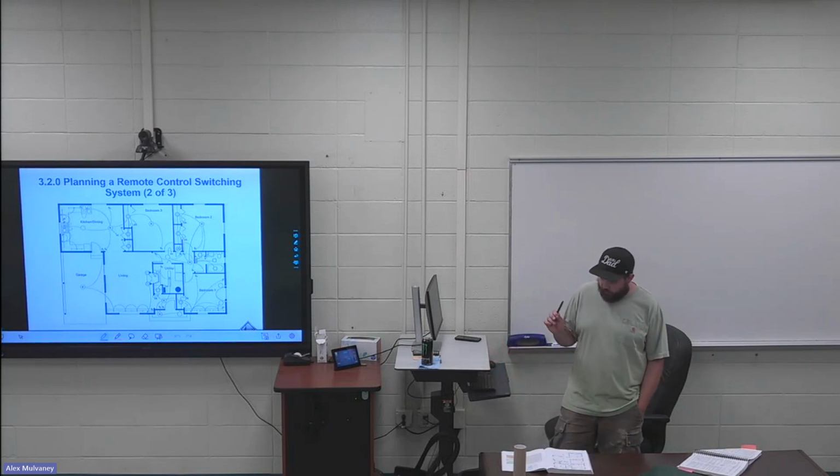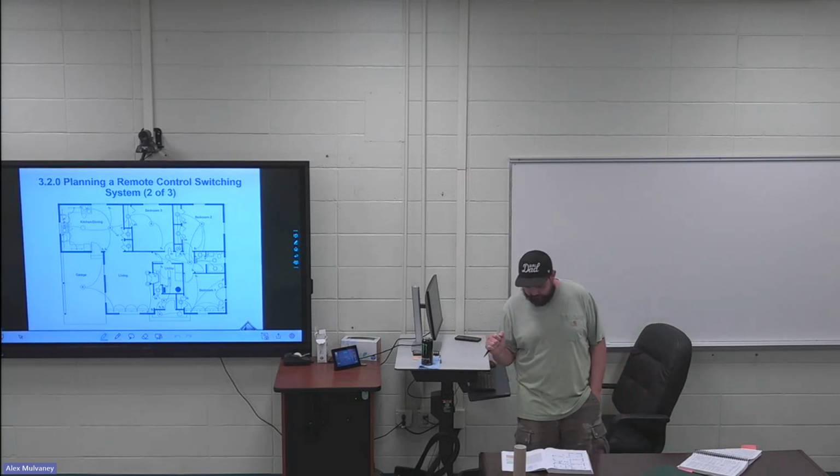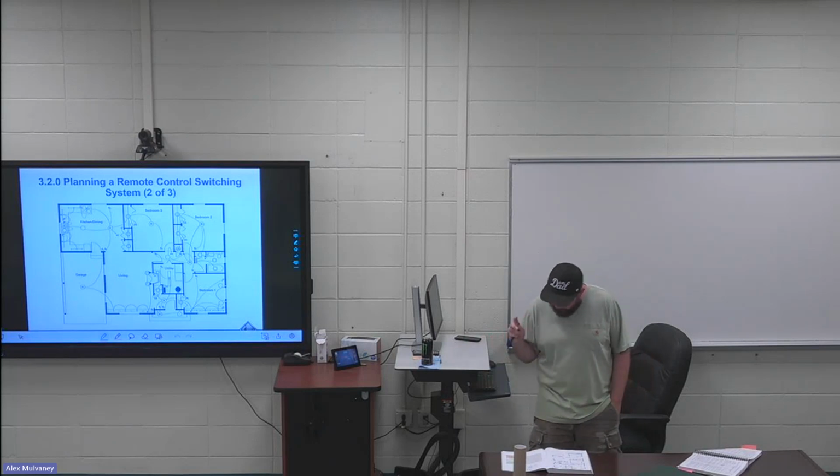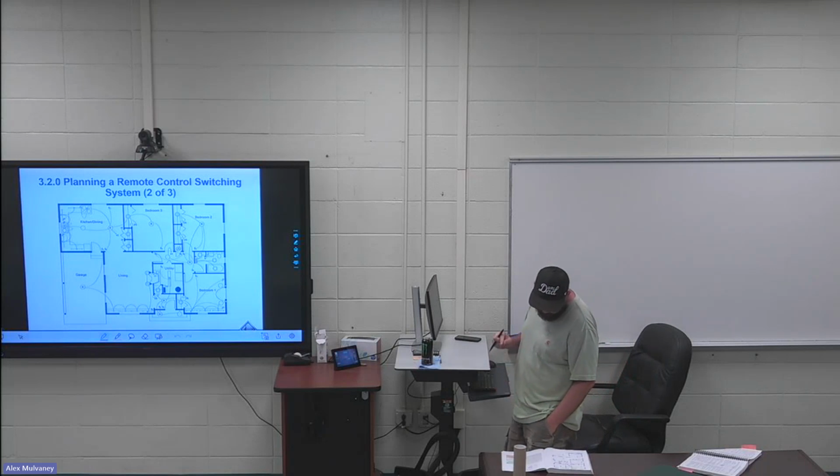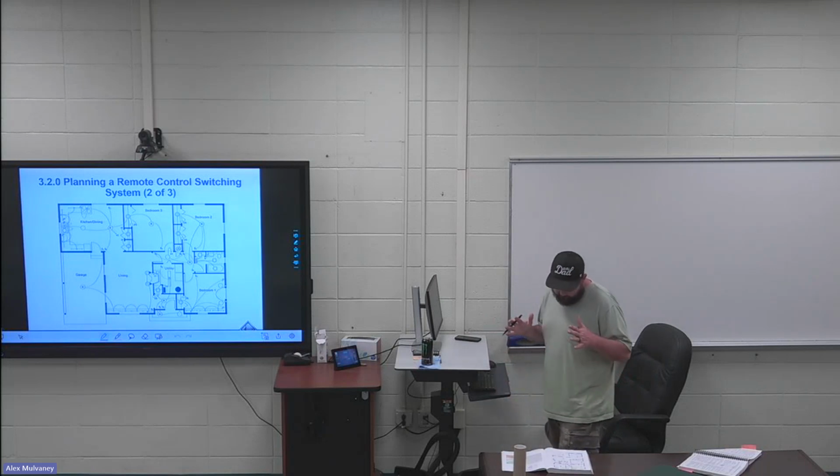I've got a section review question and an online test question that come out of this one paragraph. The low voltage wiring should also be kept apart from the high voltage wiring whenever possible. If the cables must be placed in parallel runs, they should be separated by at least 6 inches.